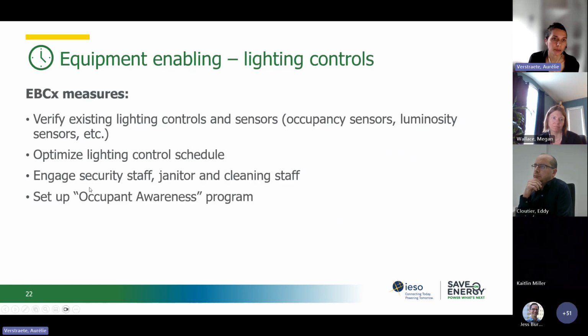The existing building commissioning measure here would be to verify existing lighting controls and sensors, and optimize the lighting control schedule. Maybe you want to engage security staff, janitor, and cleaning staff, because for lighting controls, you will see that sometimes lighting schedules are extended to match cleaning hours, which is not optimal. And finally, maybe you want to set up an occupant awareness program for the lighting control. It would encourage tenants to turn off lights when they leave their office.